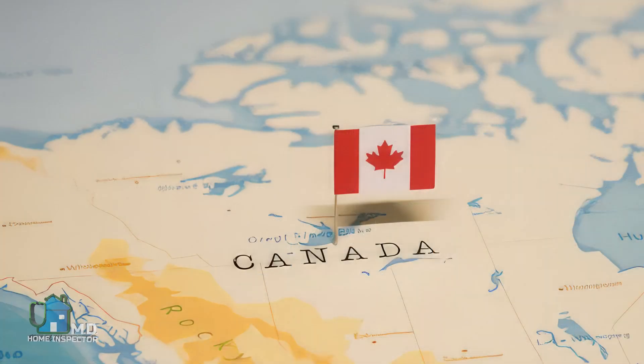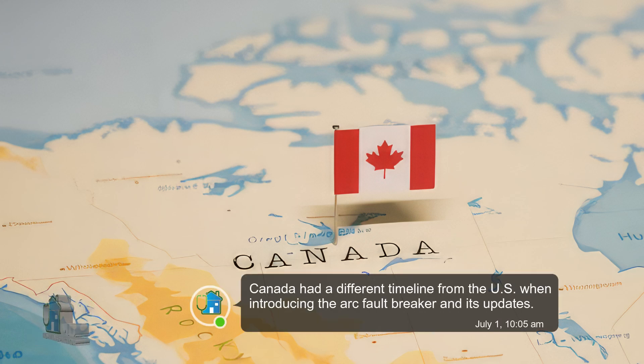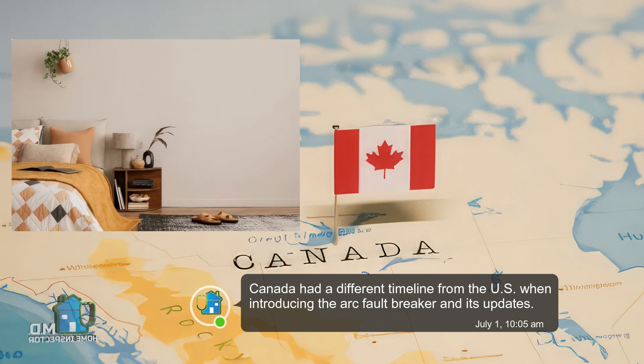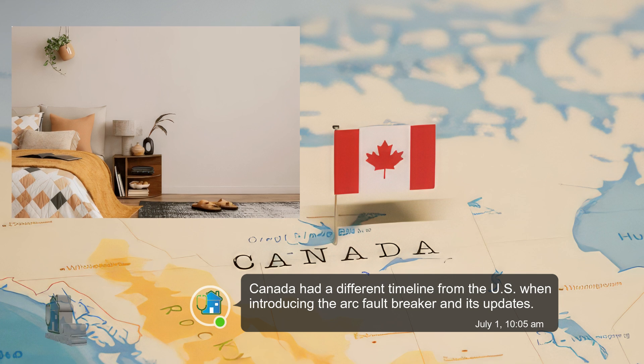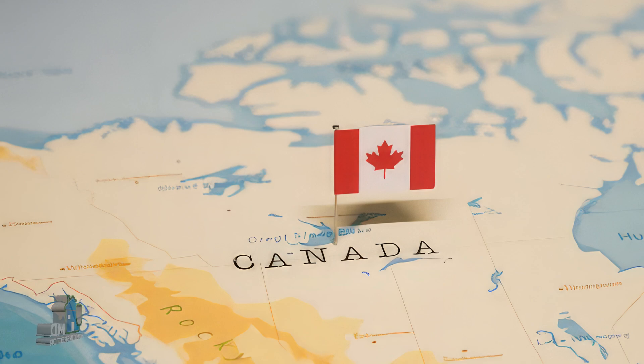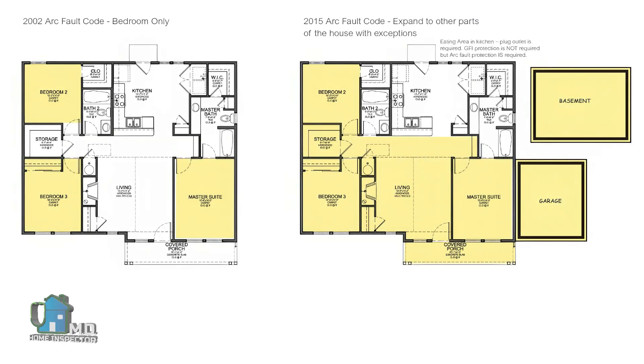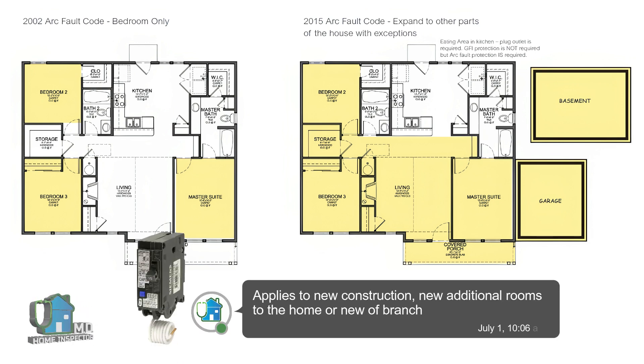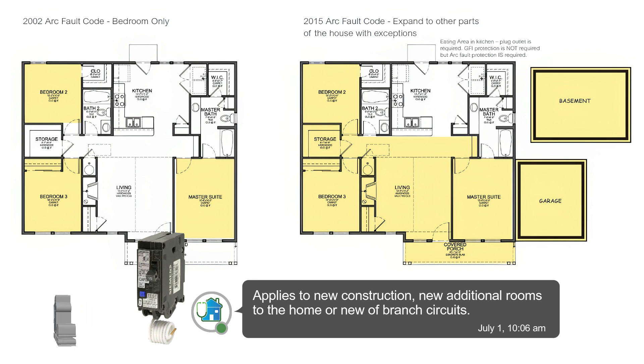Let's move on to a quick history of arc fault breakers in Canada. Arc fault breakers were first introduced in Canada in 2002, required only for new bedrooms. The next big change came in 2015 when improvements expanded their use to almost all parts of the house. This new arc fault breaker was renamed the combination arc fault breaker.